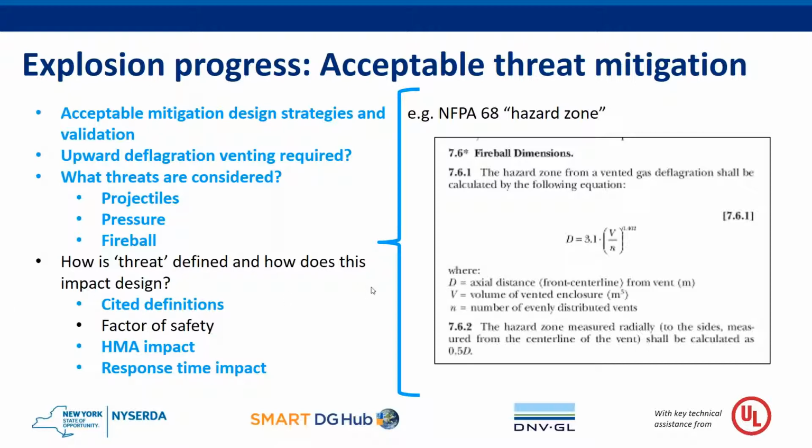As previously noted, for HMA, an additional risk analysis is not necessarily needed as long as the full engineering analysis is done on the UL 9540A testing data. And for response time impact, as previously noted, the impact of first responders is not recommended to be included in the analysis that you conduct. We're looking for the worst case scenario where there's no impact from water spray or other mitigative actions. You can go to the next slide, Danielle.